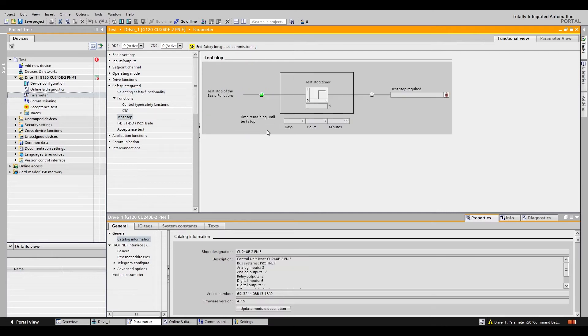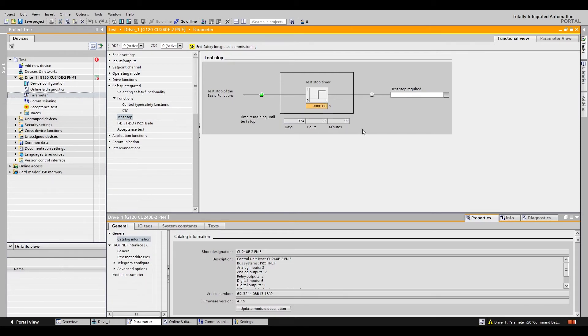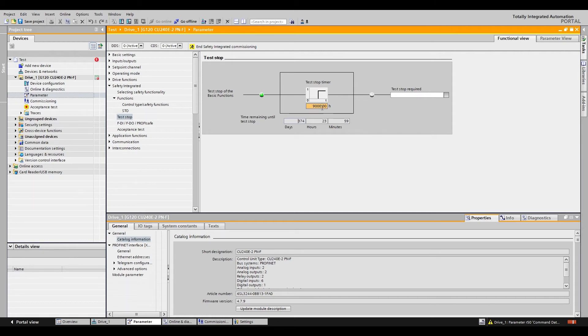The second button is test stop. By default this is eight hours but you can change it up to nine thousand hours which is roughly over a year. This will trigger an alarm if it hits the amount of hours set and it will tell you that you need to test your e-stop.